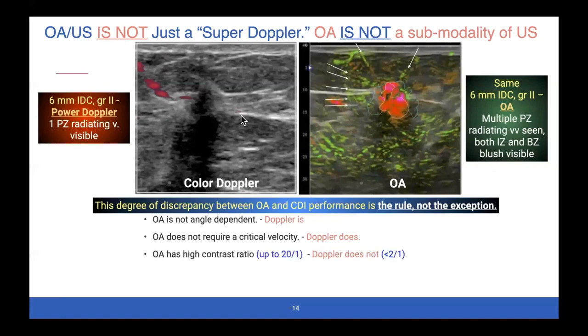The biggest difference, I think, is the contrast ratio. Doppler has a very poor contrast ratio, less than 2 to 1. And what that means is it doesn't tolerate volume averaging. So in order to see a vessel on Doppler, it pretty much has to fill a whole voxel. And so if you're looking at voxels that are, say, 500 microns in the axial plane and 1,000 microns in the horizontal planes, a vessel is going to have to be somewhere between 500 microns and 1,000 microns, almost a millimeter in size, to be visible on Doppler.